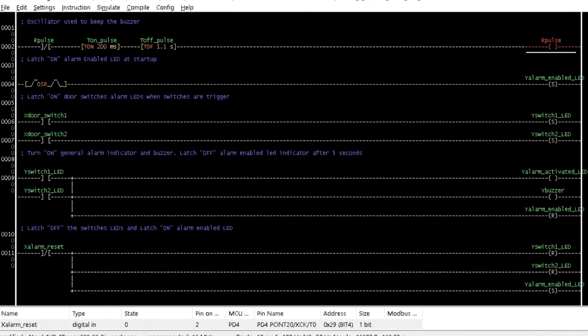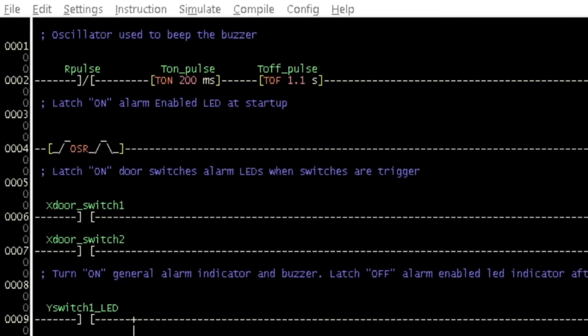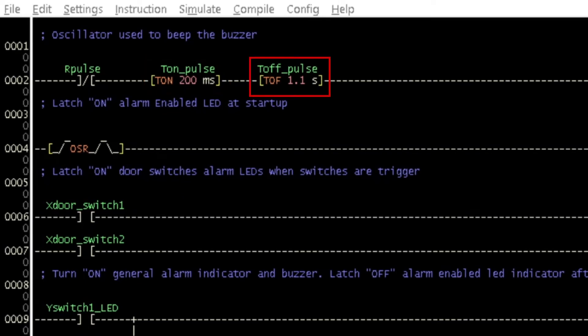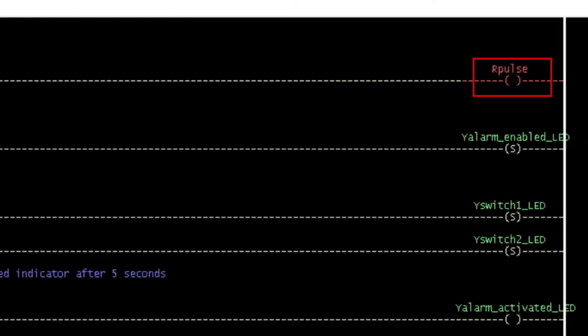Finally, let us add some of these timers to the simple alarm program from tutorial 7. Insert a rung before rung 1. Then insert a negated internal relay contact with the variable name 'Rpulse', a turn on delay timer with the variable name 'Ton_pulse', a turn off delay timer with the variable name 'Toff_pulse', and an internal relay coil with the variable name matching the contact.